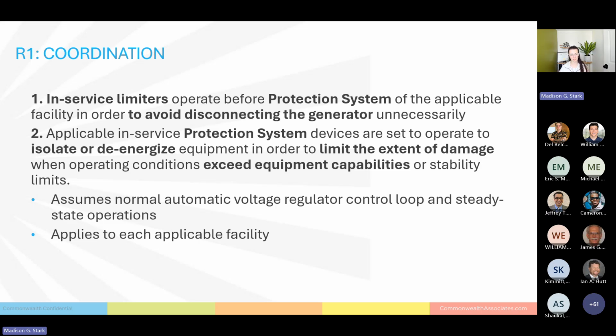And this coordination applies to each applicable facility. So if you have multiple facilities that are connected to a common bus, each of these facilities is required to be coordinated appropriately. You can't have half your site coordinated and half your site uncoordinated. And again, just hitting that order of operations, we want the limiters to act first to curtail generation to avoid disconnecting the generator. And then in the event that we can't curtail generation, the protection system is what kicks in.